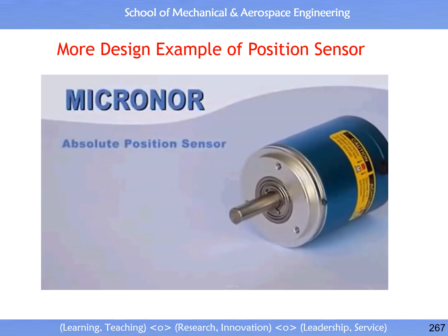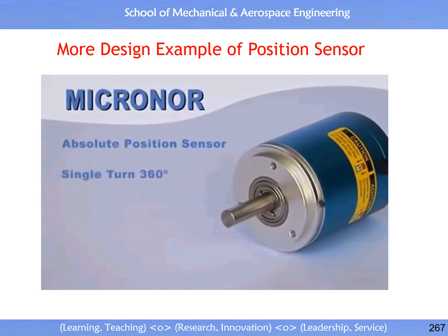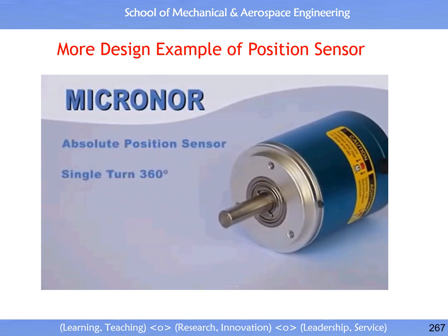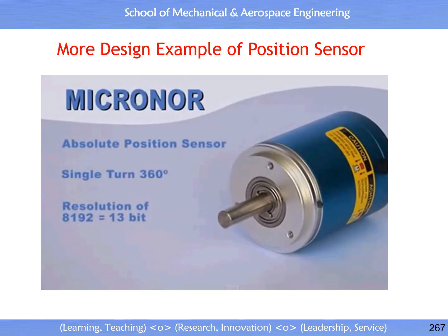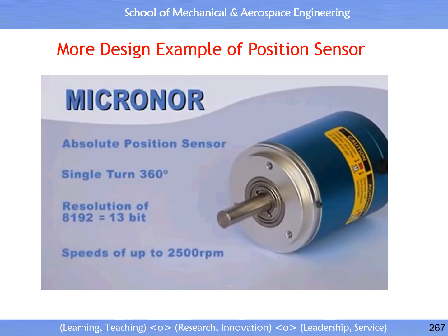This is an absolute position sensor. Single turn with a 360-degree continuous reading and a resolution of 8,192. It keeps track of speeds in excess of 2,500 RPM.